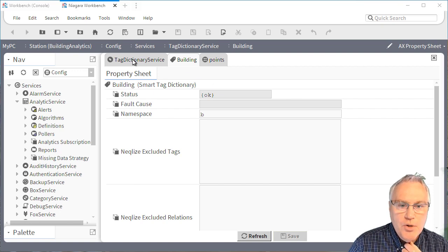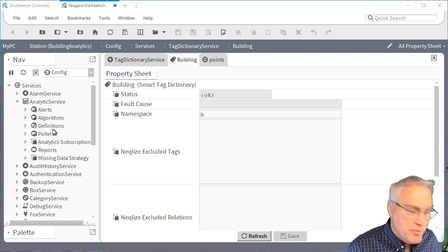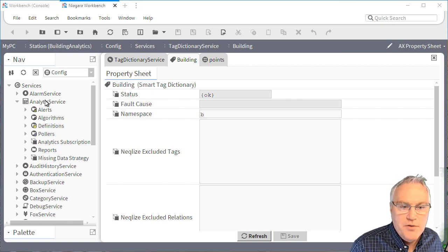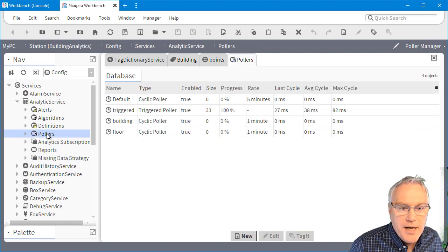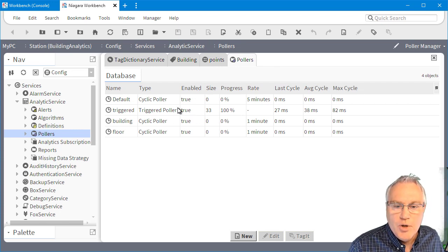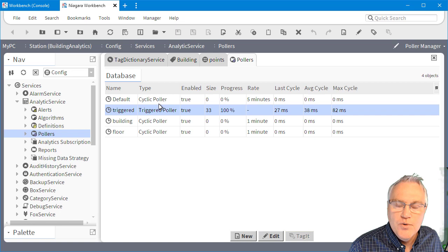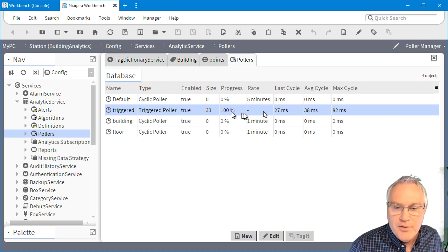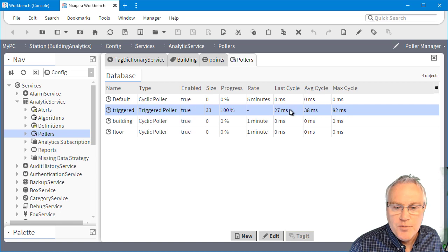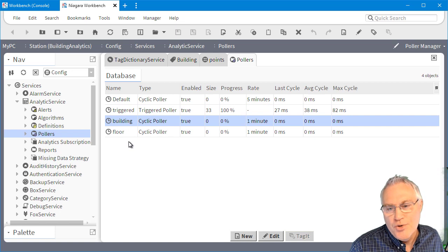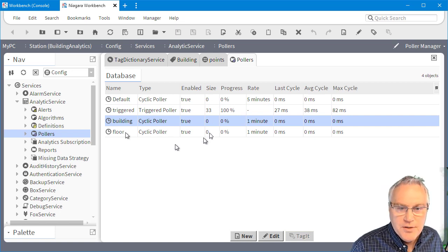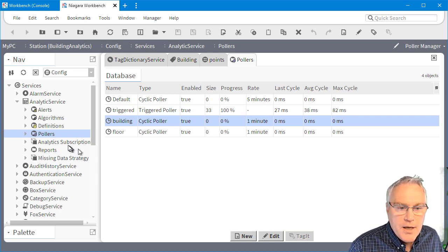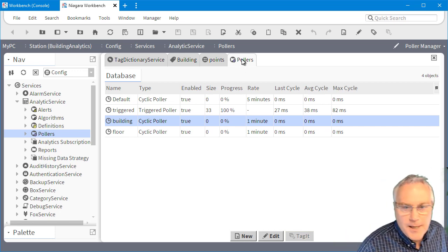This is a station I put together for the demonstration. Let's walk through how that goes. To quickly go over some components: in my analytics service that I have running, I have a series of pollers. These pollers are going to execute the request for the analytics, so I have them all manual. Usually when I build things out, I do manual so I can see the actual time it takes to do those processes. So usually I would break it up into a building floor, AHU, or room level for these cyclical pollers.